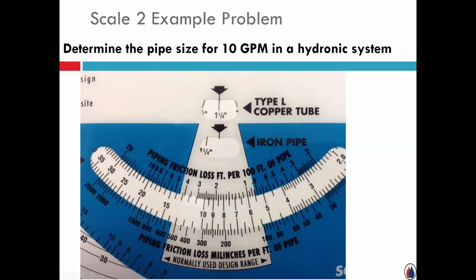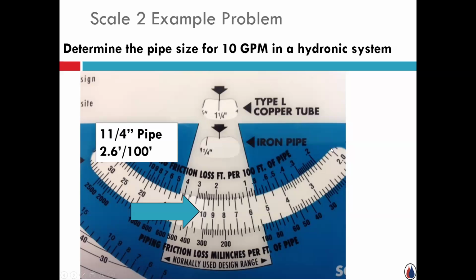And if I'm solving for copper pipe for this example, what I want to do is line up the particular pipe size that I'm going to select. I can't just have it off of this pointer here. It's got to be lined up exactly. So in this example, 10 gallons a minute kind of falls within that white band. It's kind of a good industry standard in terms of selection. I line up the copper, and all it's going to tell me is the pressure drop. So in this case, 10 gallons a minute flowing through 1¼ inch copper pipe is going to offer 2.6 feet of frictional resistance for every 100 feet of pipe. It's as simple as that.